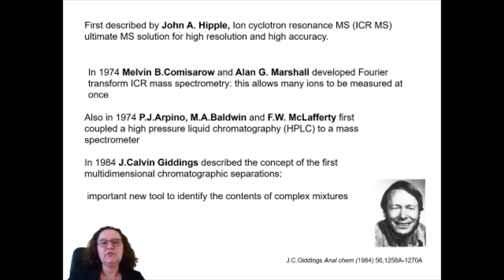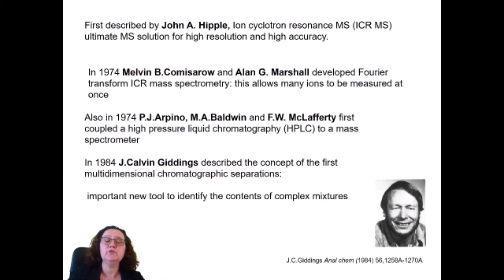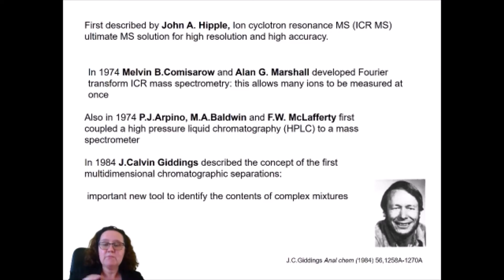New improvements came in the late 60s, 70s, and 80s. Hipple developed something called ion cyclotron resonance mass spectrometry, which really improved the resolution and accuracy of the instruments. In the mid-70s, Comisarow and Marshall developed something called Fourier transform ICR mass spectrometry, and that allowed many different ions to be measured at the same time.